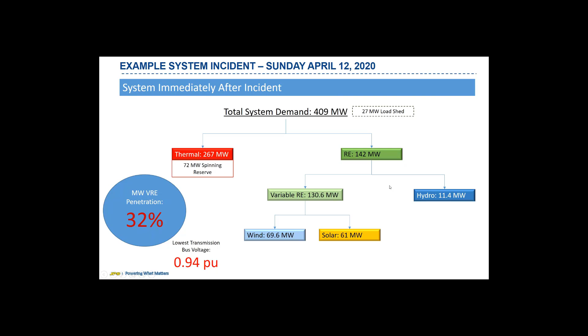So the result of all these actions, the loss of the generating plant and the loss of the transmission line, is that our lowest bus voltage was around 0.94 pu. This is outside of our tolerance, which is plus or minus 5%. So at this point, we have a risk of other generating units tripping. So some action has to be taken immediately.